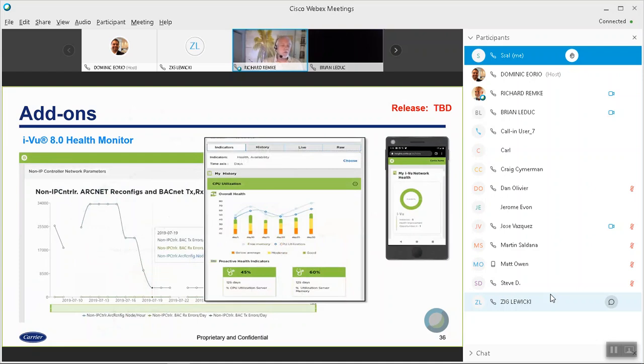Again, this is not really designed or meant for the typical end user. If you've got a big end user that has thousands of controllers, they may be really interested in these kinds of reports. But from a service perspective, you can give reports on how well the communication is doing. If you've got issues going back and forth between controllers, it'll tell you, and it tells you if you're up to rev on your cumulative updates. It tells you if the processor that is running the i-Vu server has issues, or if it maybe needs more memory, or other things enabled on it. So it's a very powerful tool.